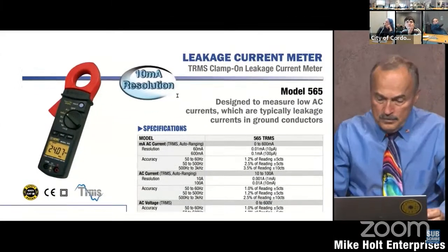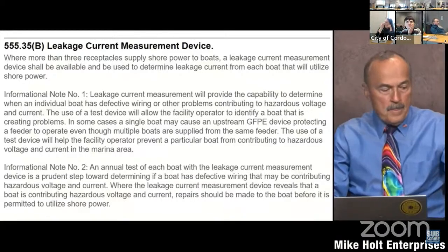So now let's think about this. Go back here. I run a feeder, 100 milliampere ground fault protection of equipment. I put the pedestal, I put breakers, I put 30 milliamperes protection, and I have it all worked out. Let's just say that we had 4 shore power outlets, and each one had 27 milliamperes of leakage. Well, 4 times 27 comes up to be 108 milliamperes. Well, since it's 27 milliamperes each, that's not a problem because none of those 4 breakers are going to trip. But because the cumulative total of the 4 equals more than 100 milliamperes, the feeder drops them all out.